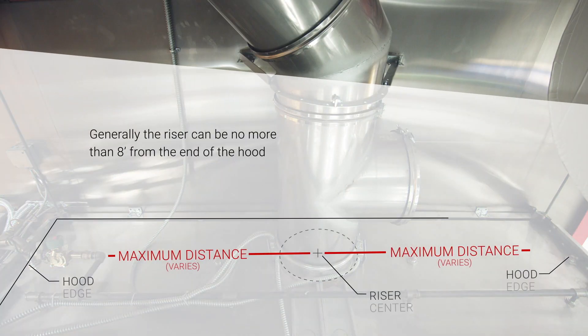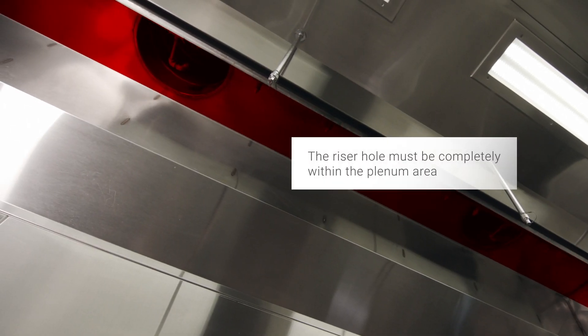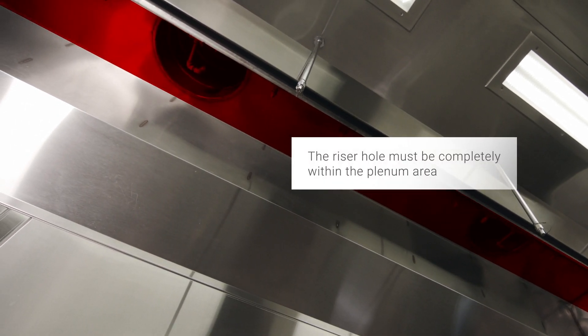To install a field installed riser, locate the desired position of the riser on top of the hood, ensuring the location complies with the hood manufacturer's requirements. Make sure that the hole location is inside the plenum area before cutting.